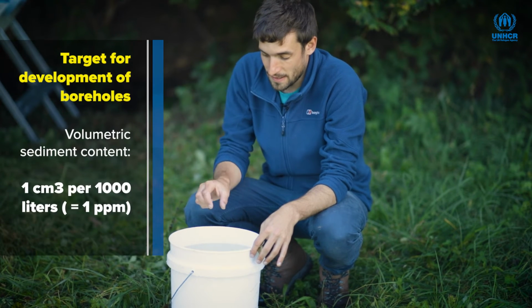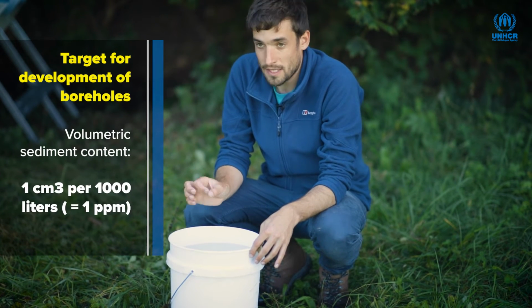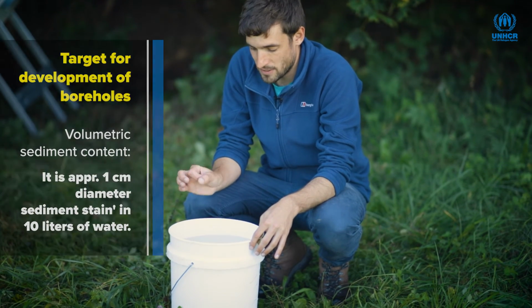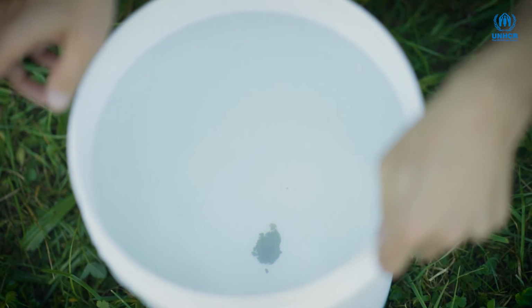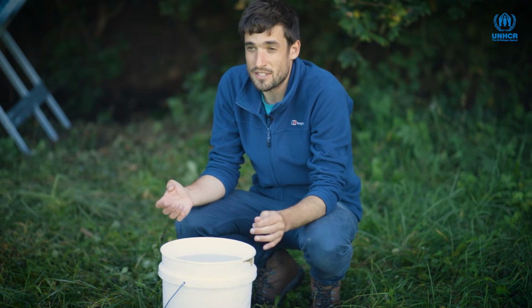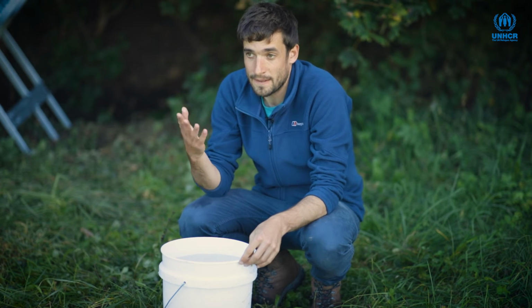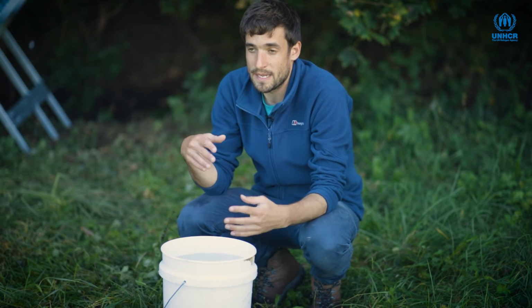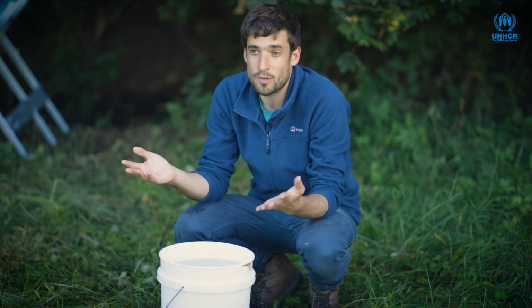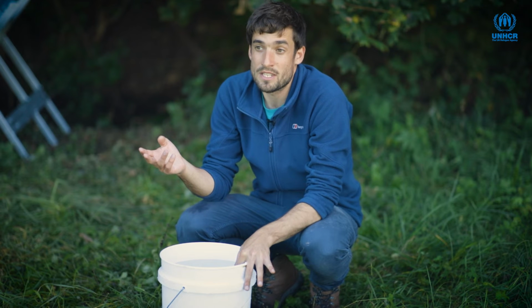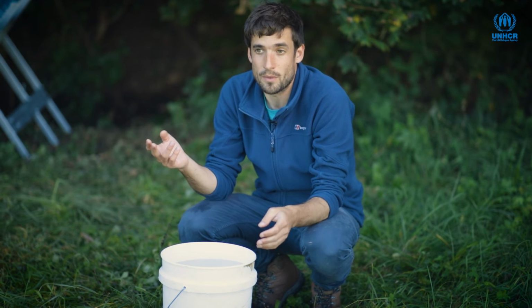So what we have here is a circle of sediment in the bottom of the bucket that's about 2 or 3 centimetres in diameter. So that's indicating that we have too much sediment in the water, and this could potentially cause problems with pumping equipment, and pipes will be exposed to increased abrasion, which could lead to premature breakdown of the pumping equipment.